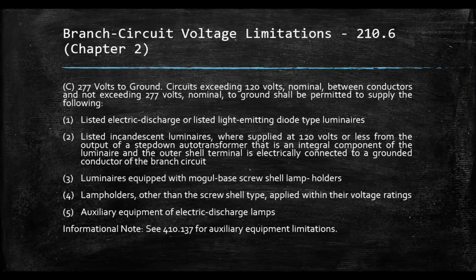Number 2, listed incandescent luminaires where supplied at 120 volts or less from the output of a step-down transformer that is an integral component of the luminaire and the outer shell terminal is electrically connected to a grounded conductor of the branch circuit. Number 3, luminaires equipped with mogul-base screw shell lampholders. Number 4, lampholders other than the screw shell type applied within their voltage ratings. And number 5, auxiliary equipment of electric discharge lamps.